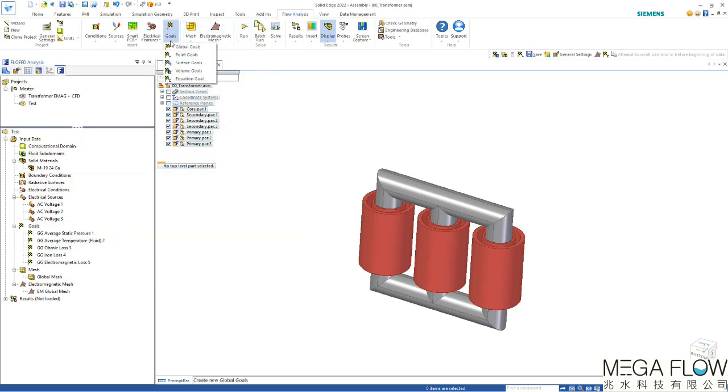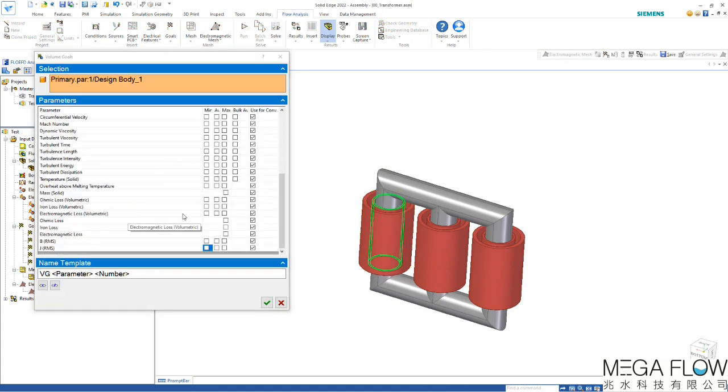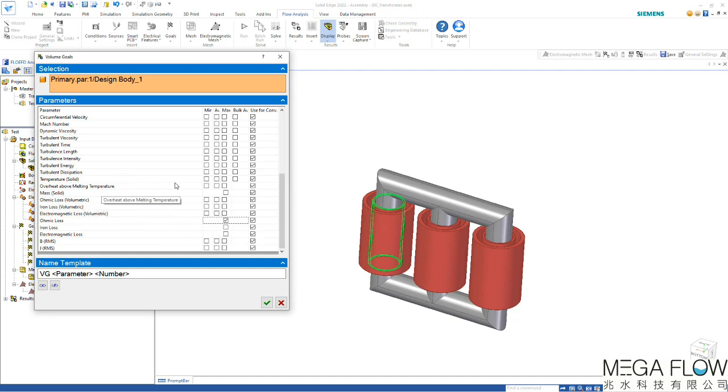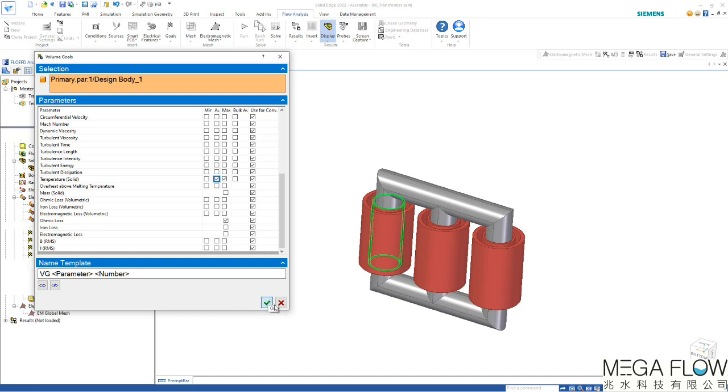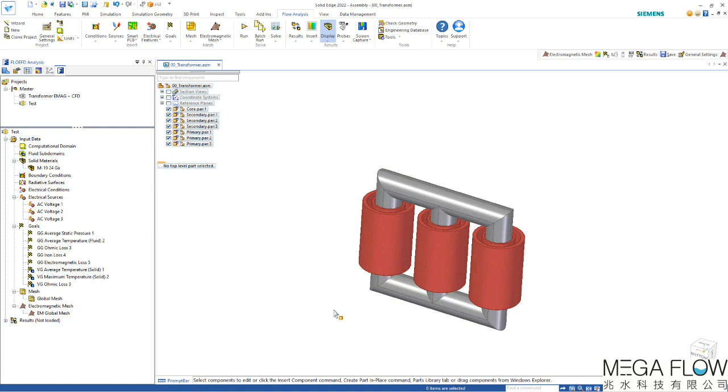We could also specify volume goals onto the individual coils to know what are their specific iron losses or ohmic losses. Since we're having current going through here there will be only ohmic losses. We can also look at the temperature of the solid at this point, for example the maximum temperature of that coil or average temperature. Defining these goals on all the individual components gives information about how hot directly these coils are and they're used for convergence, making sure that the results are converged and accurate.